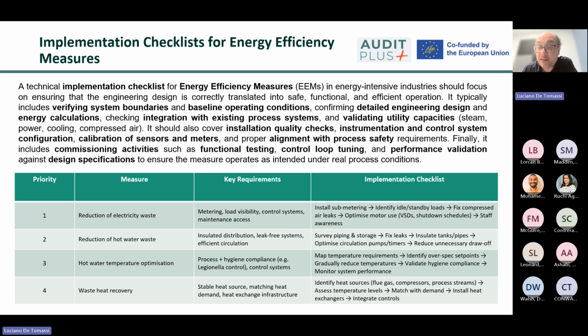The detailed engineering design should be reviewed to ensure that the proposed solution is technically feasible and capable of achieving the intended performance. Key checks include verification of energy and mass balance calculations, confirmation of equipment sizing and capacity requirements, review of thermal and electrical load calculations, assessment of process integration impacts, verification of pipework, ductwork, hydraulic and electrical designs, confirmation of equipment specifications, and performance guarantees.